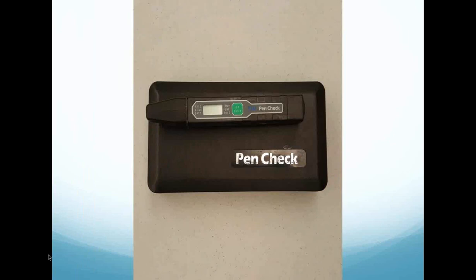This is a vibration analyzer. It's made by a company that called it a pen check, and what they did is they built this little device, and I want you to be careful of jumping in and buying a vibration analyzer to check your steam traps. You need to have a little bit of background, and a little bit of familiarity with steam before you jump in with a vibration analyzer to start checking your steam traps. This has not gained in popularity as much as the other devices like the ones that UE have available. I wanted you to know that this type of technology is available, but I also want you to know that you need some experience to be able to discern what it's telling you.